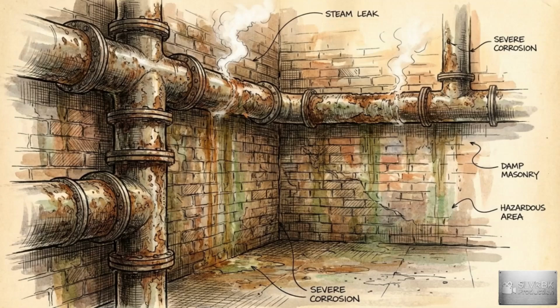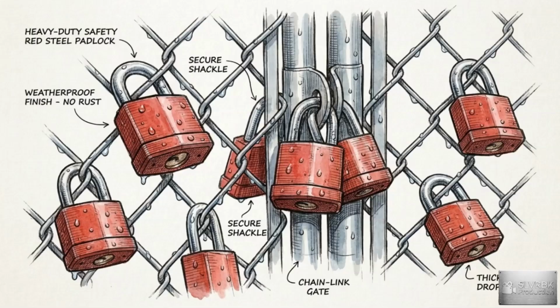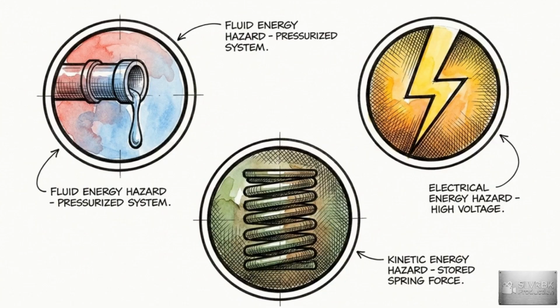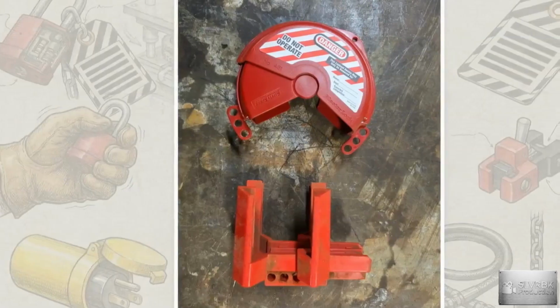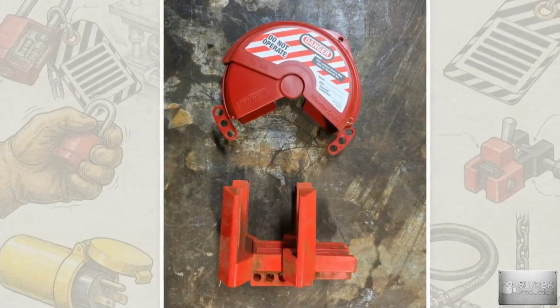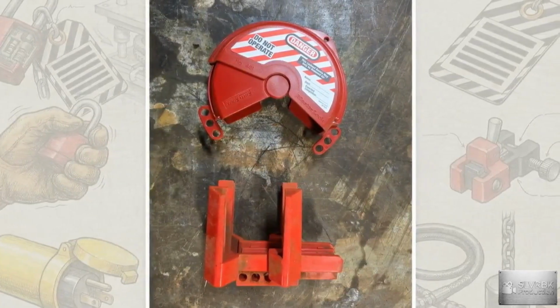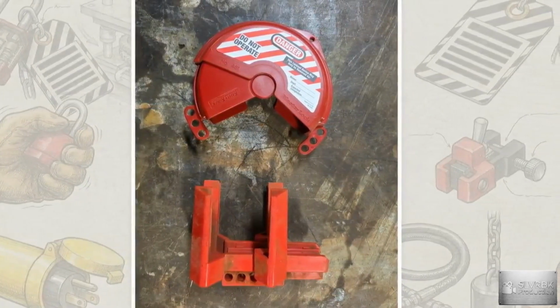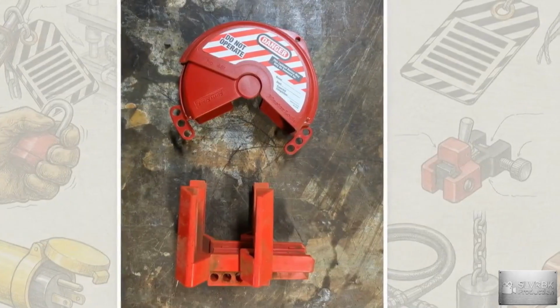Because industrial environments are highly corrosive and volatile, OSHA requires all lockout hardware to be exceptionally durable, capable of withstanding prolonged exposure to weather, dampness, and chemical environments. Isolating hardware is highly specialized for specific energy sources. For fluid and gas lines, devices like this red plastic clamshell are designed to completely encapsulate ball valves, making the handle physically impossible to turn.